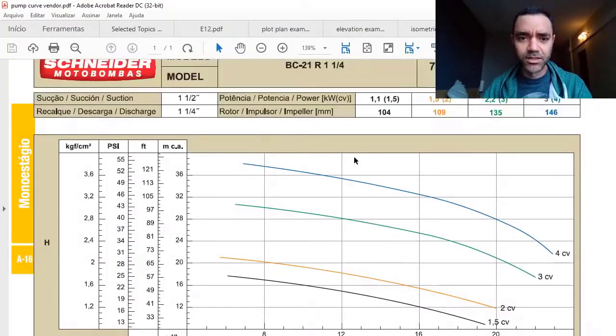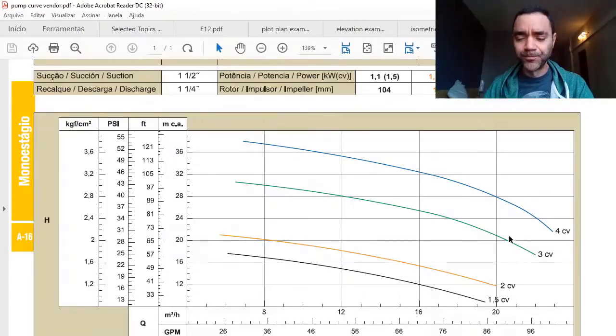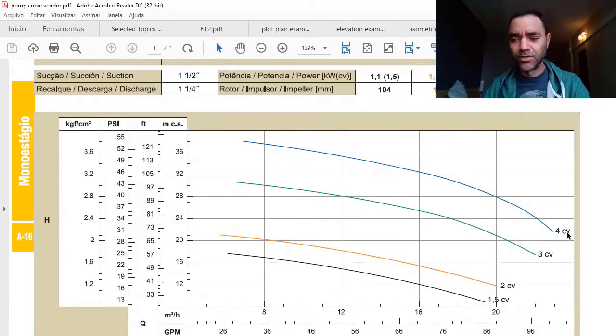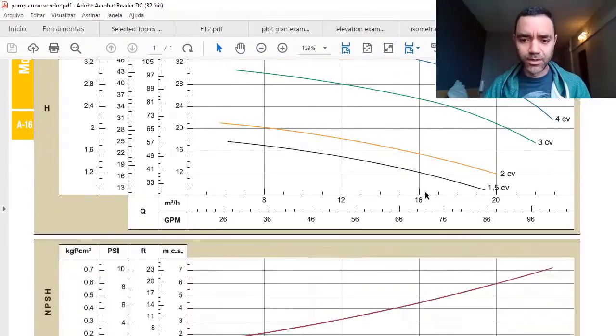We have here the curves according to each impeller size—you see blue is 146 millimeters, 135 millimeters, 109 millimeters. We've seen that the power increases as we increase the impeller, because for the same flow we have more head, so we're increasing the power needed to run your pump.